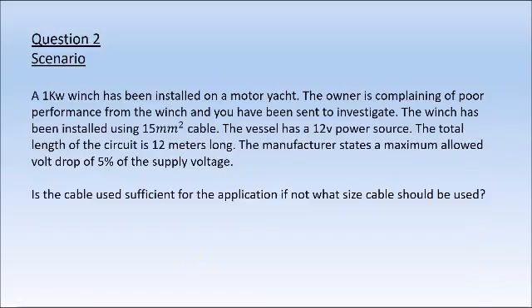In the second scenario — there's potential for two different types of question from this subject in an exam — a 1-kilowatt winch has been installed on a motor yacht. The owner is complaining of poor performance and you've been sent to investigate. The winch has been installed using a 15-millimeter square cable. The vessel has a 12-volt power source, and the total length of circuit is 12 meters long. The manufacturer states a maximum allowed volt drop of 5% of the supply voltage. You need to calculate: is the cable sufficient for this application, and if it isn't, what size should be used?